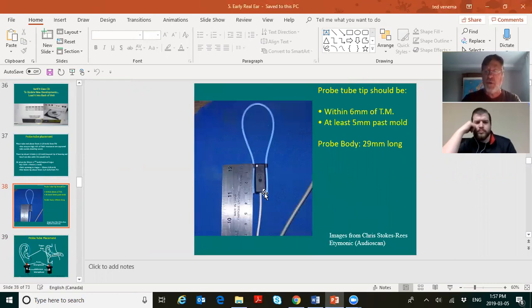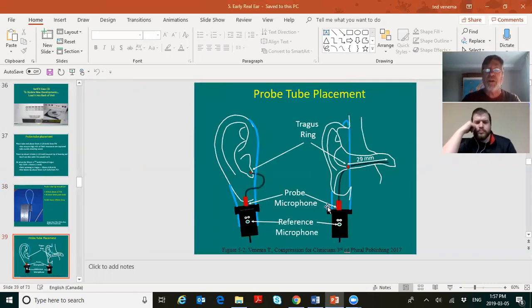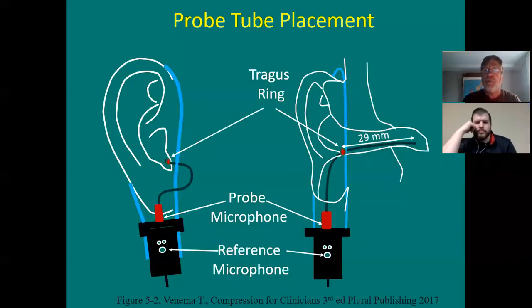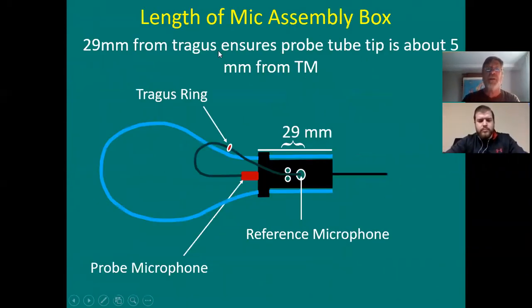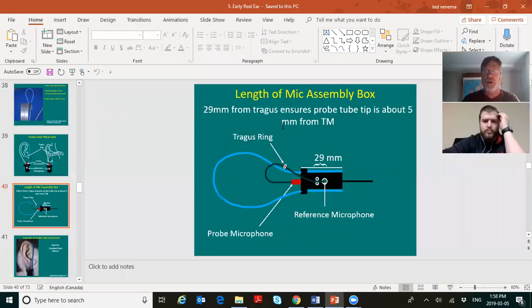That way you knew that when you were putting the tube in the guy's ear, when the ring was at the tragus, from the tragus, 29 millimeters inward will leave the tip of the tube about 1/4 of an inch from the drum. And that essentially is the purpose of all of that. So the length of the mic assembly box is done that way, whether in Costco systems or whatever.